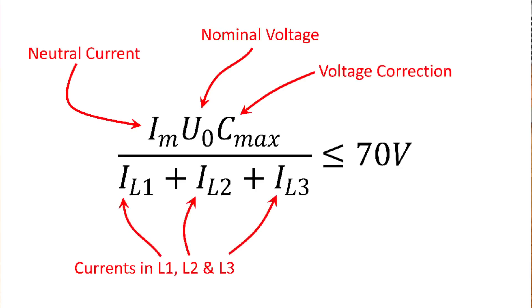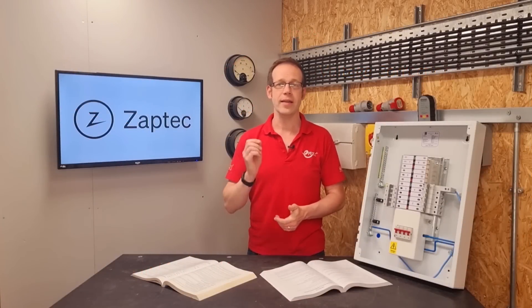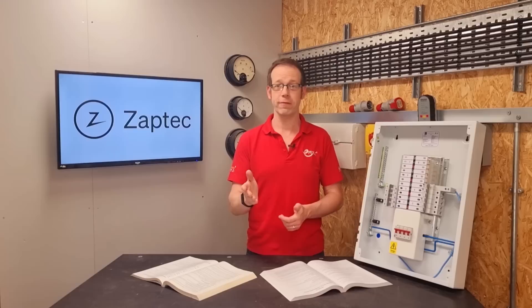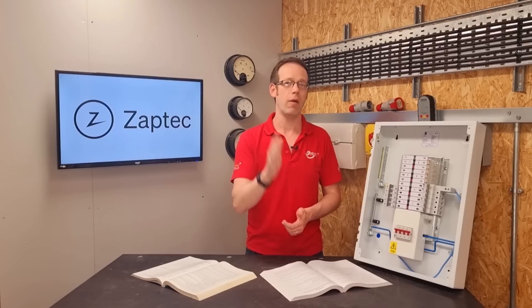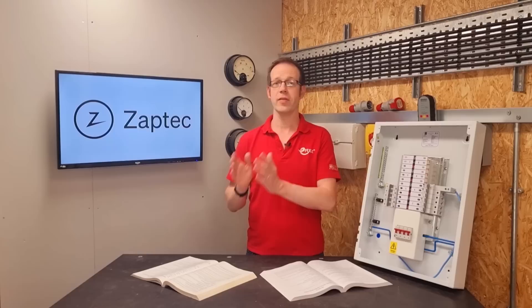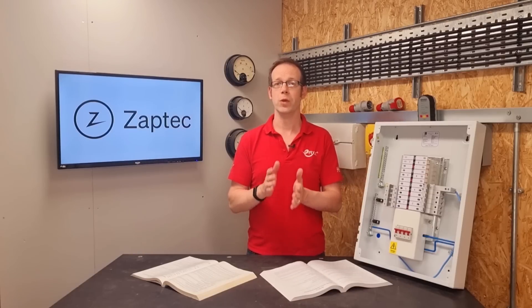These are multiplied together and then the division part on the bottom row is just the three currents in the three phases added together. So all this is doing is indicating that the maths on the left should be less than or equal to 70 volts. So the annex is saying that if that formula is true and the maths is less than or equal to 70 volts when a PEN fault occurs, then the installation will be safe. Importantly however, it's also saying that the opposite is the case, and if the maths on the left is more than 70 volts then the installation will not be safe.